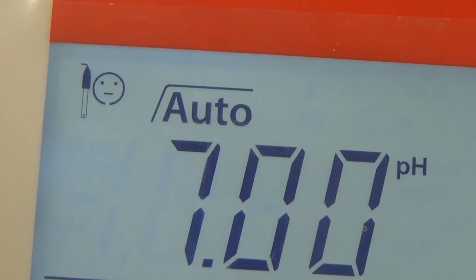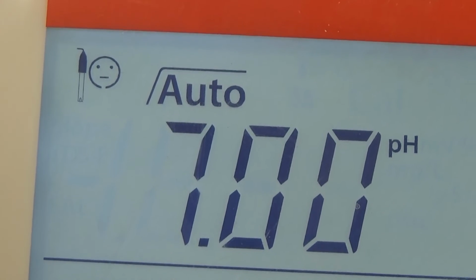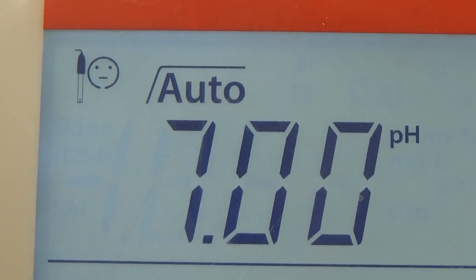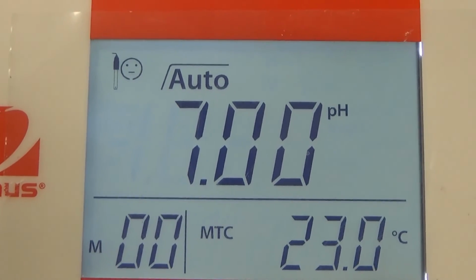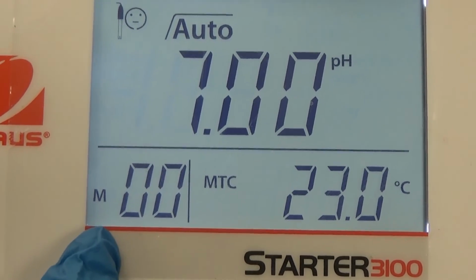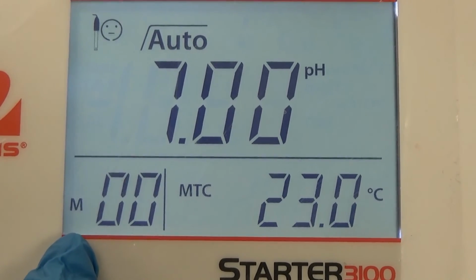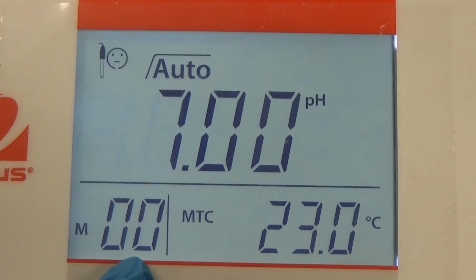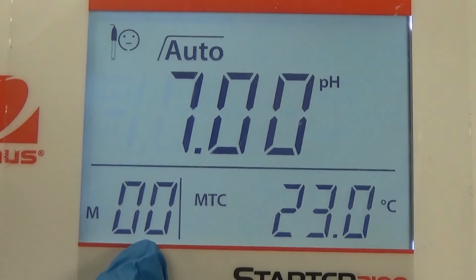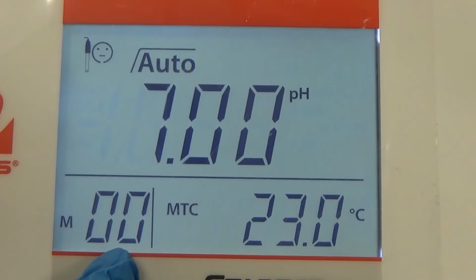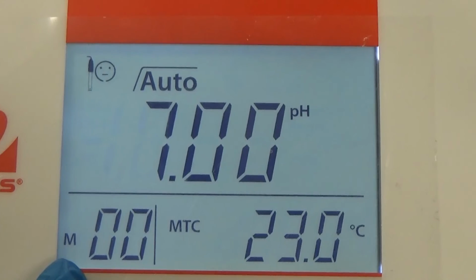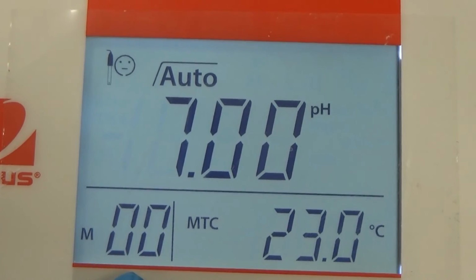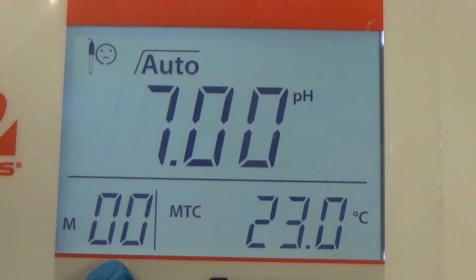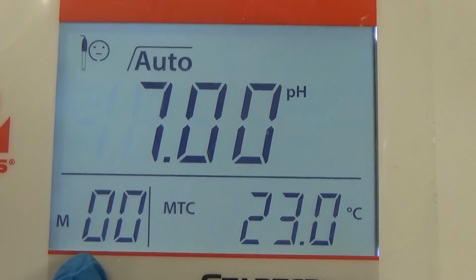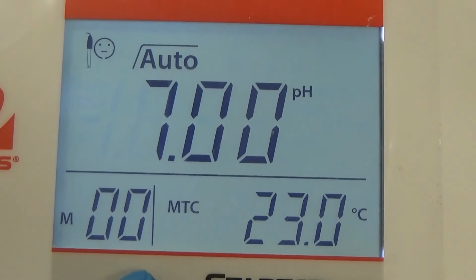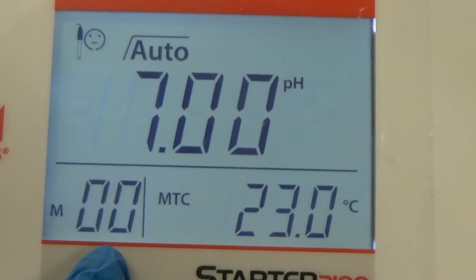Whenever you are reading the pH, it will fluctuate, and the auto will start flashing when it is stable. The M here, I believe, is for memory, so if you hit memory at any point, it will store it as 1 or 2 or 3, however many points you had saved. But like I mentioned, you won't need to hit the memory button. When you do the calibration, the numbers here will change based on what point you have done in the 3-point calibration. So if it's your first sample, it'll say M01 or M02 or M03 for the 3 different buffers.